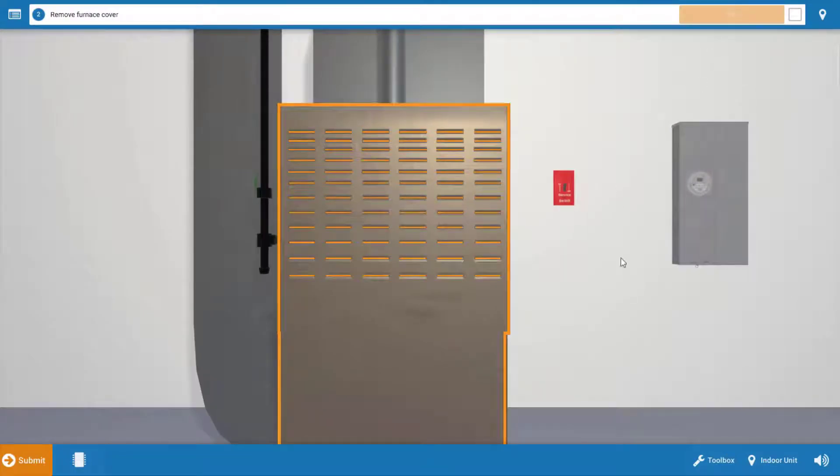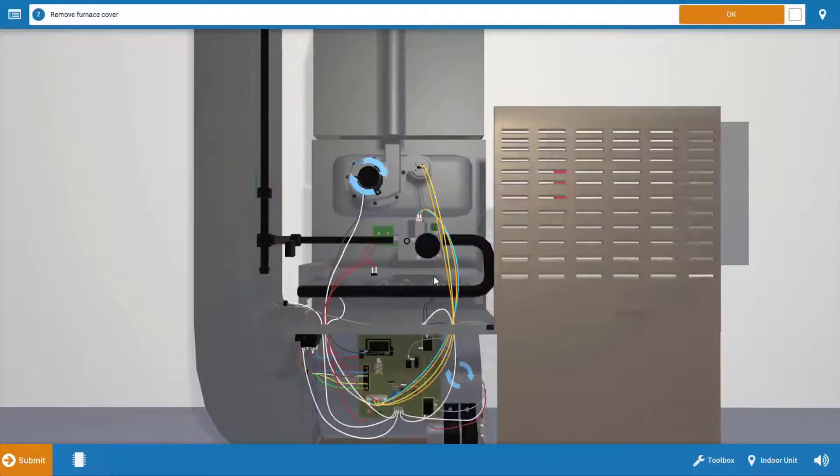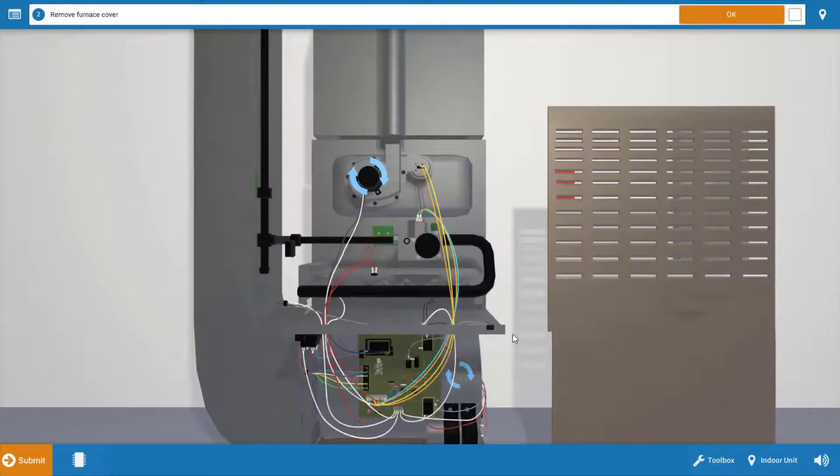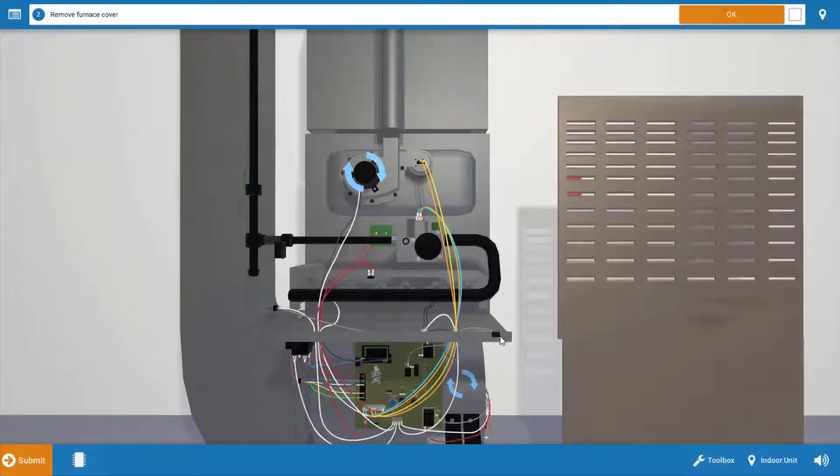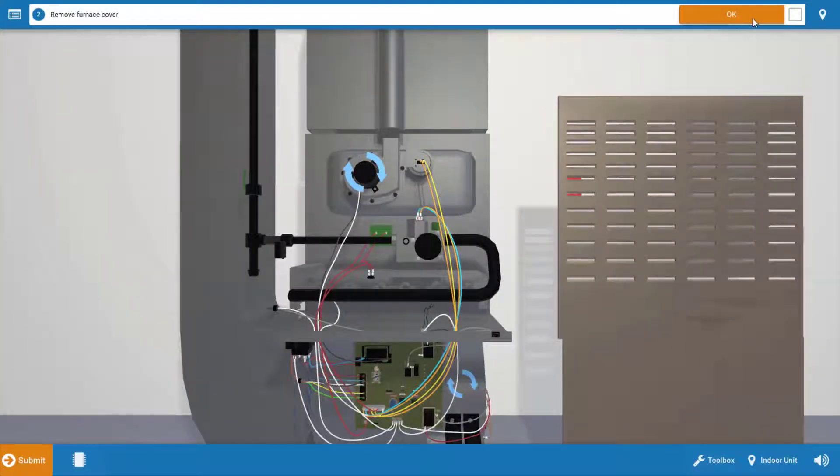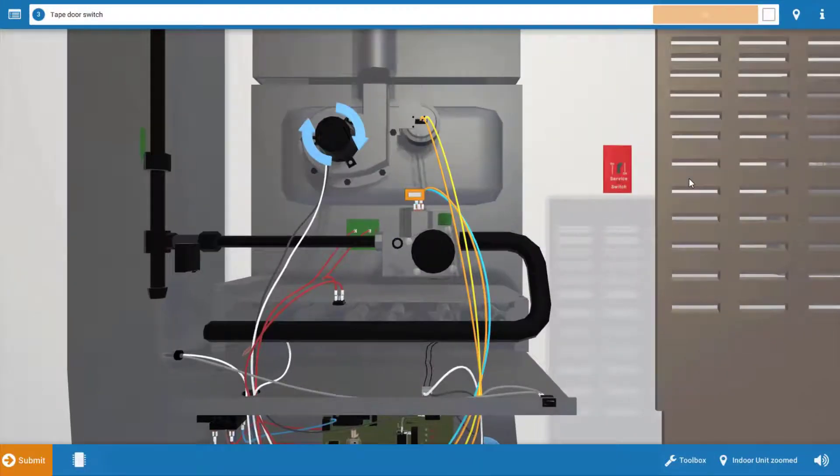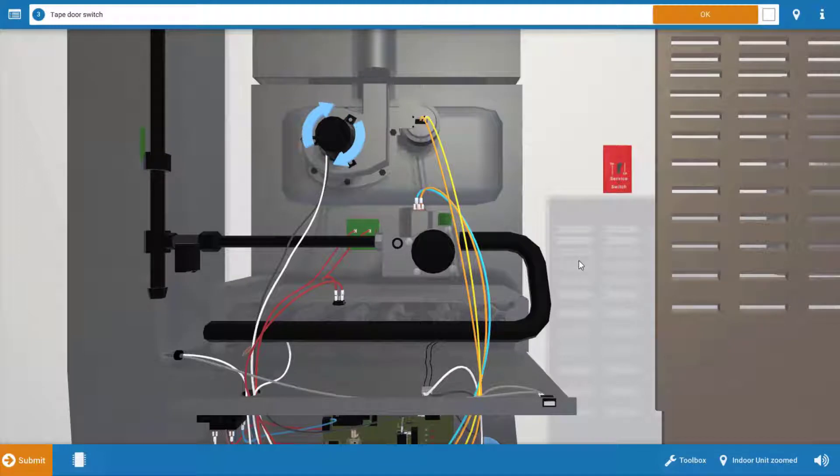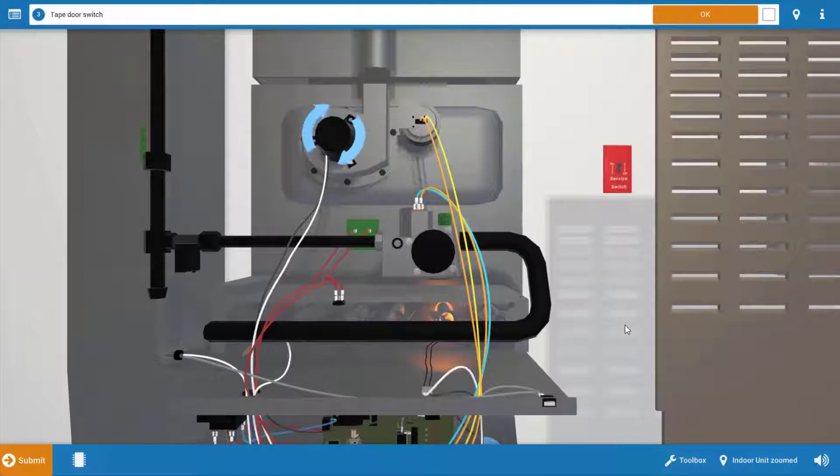Our next step is to remove the cover from the furnace and see which loads are operating. But when we do this, this door switch located right here on the right is going to open its contacts and break power to the furnace. So it's going to be necessary to tape this door switch in. Simply click on this piece of tape up here, and that'll place it over the door switch, ensuring its contacts are closed and that power is being received at the furnace.